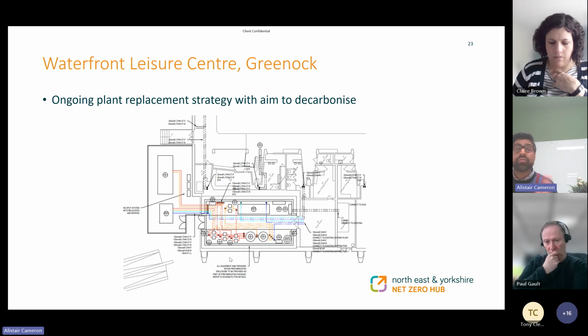And these chillers are used throughout the year. We always need to generate ice, even in the coldest depths of winter. The ice chiller is operating at -12 degrees in order to maintain the ice floor. So the chillers are on all the time, and they're always rejecting heat. So let's get that heat from the chiller and transfer it to the swimming pool, which again has a 365-day heating demand, irrespective of the temperature outside.